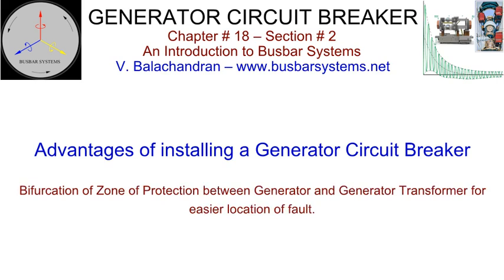Without a generator circuit breaker, the generator neutral point to the terminal of the HV circuit breaker connected to the generator transformer, and tap-offs in between to the auxiliary transformer, excitation transformer, surge protection voltage transformer cubicles, will comprise a common zone of protection for isolation by the HV breaker in the event of a fault within the zone. With the generator circuit breaker, it is possible to split the zone into two. One zone comprises all elements from the terminal of the HV breaker to the terminal of the generator circuit breaker on generator transformer side, comprising generator transformer, auxiliary transformers, surge protection and voltage transformer cubicle, if separately installed, and any other tap-off in between. The fault in the respective zones can be isolated, thereby minimizing the time taken to identify the fault and synchronizing the unit back in service. For generators starting up and shutting down, only the generator circuit breaker needs to be operated.